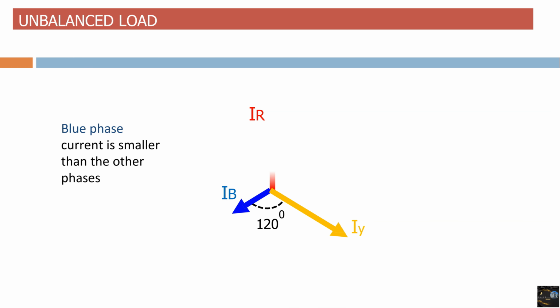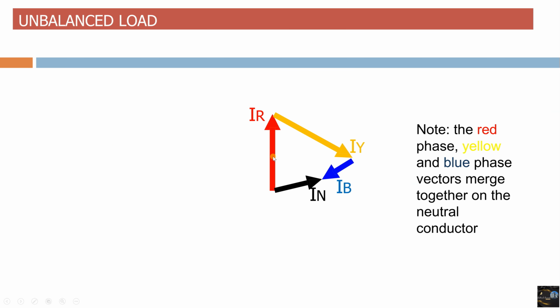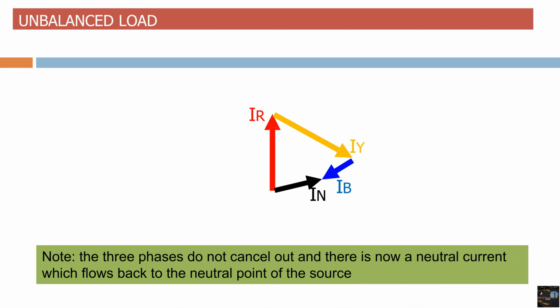Now let's see our second condition, that is unbalanced load. You can see that the magnitudes of the three phases are not equal, but they are still 120 degrees apart from each other. Here, the blue phase is smaller than the other two phases. And if we take the summation, you can see that in this case, that is in unbalanced load, there is always a neutral current that flows. Thus, the three phases don't cancel out and there is now a neutral current which flows back to the neutral point of the source.